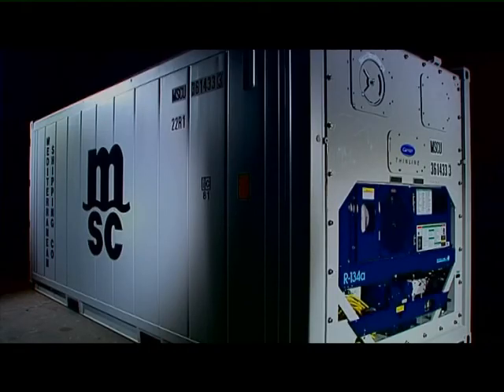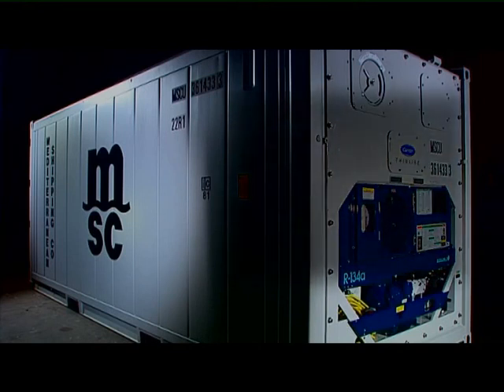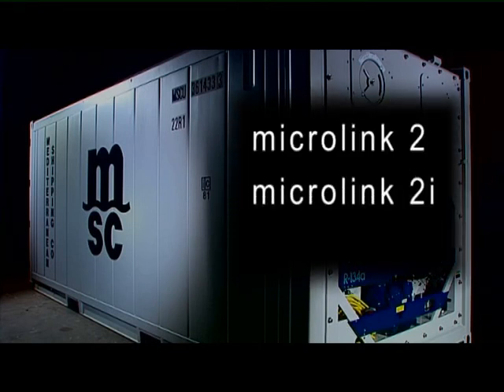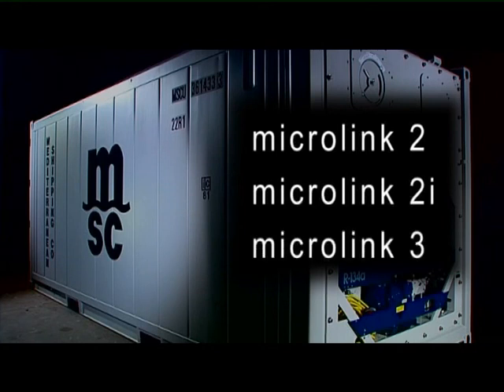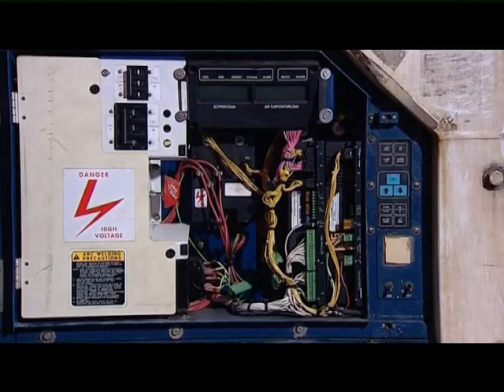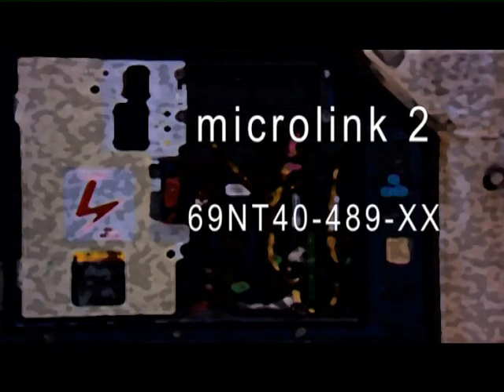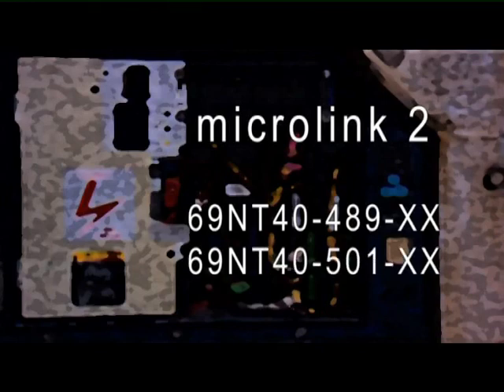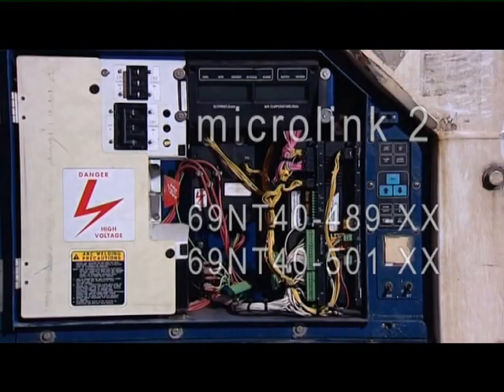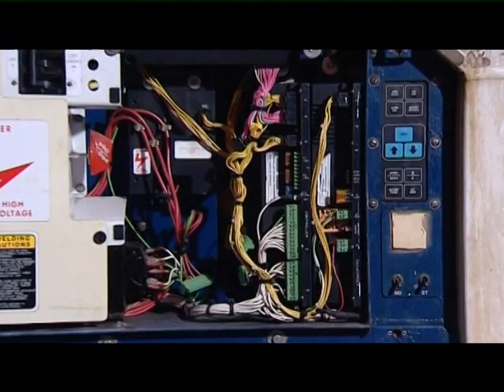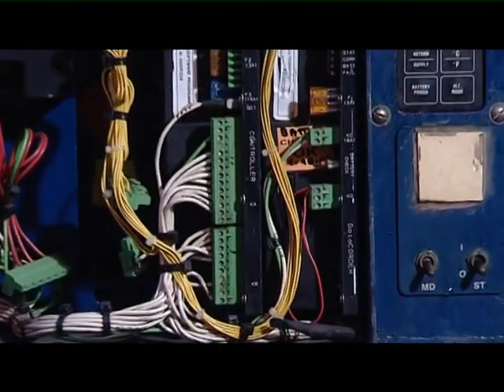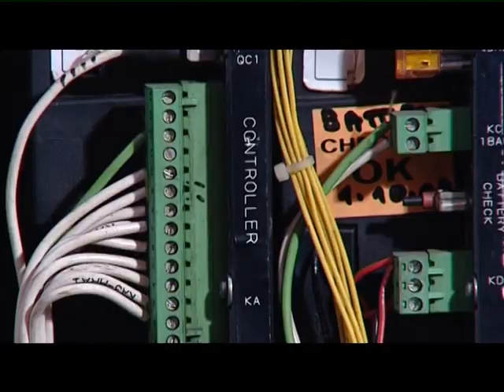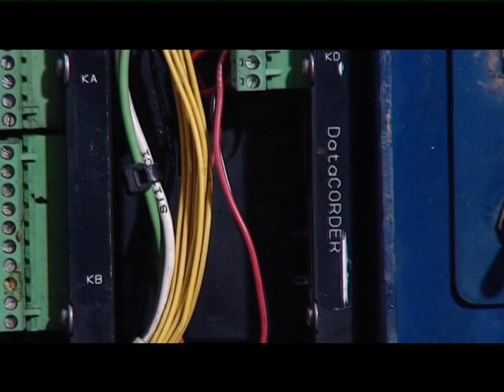We have three types of Reefer units fitted with the controller: Microlink 2, Microlink 2i, and Microlink 3. Microlink 2 units are the 69NT40-489 and 69NT40-501 models. These models have two components mounted in the electrical box: the controller and the data recorder. The data recorder is an option on these models, and it is not always fitted.